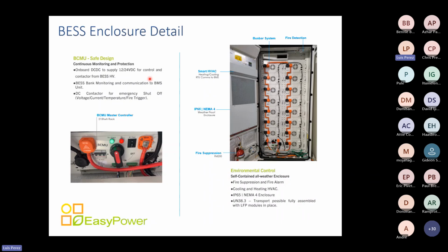So many of our competitors, and ourselves, have moved to systems with better thermal control. You can see we have an HVAC mounted on the door, physically pushing air through a set of conduits and baffles inside the batteries to keep a steady temperature profile. The same solution can be engineered with a water-cooled system, but it's more complex, costlier, and needs more maintenance.